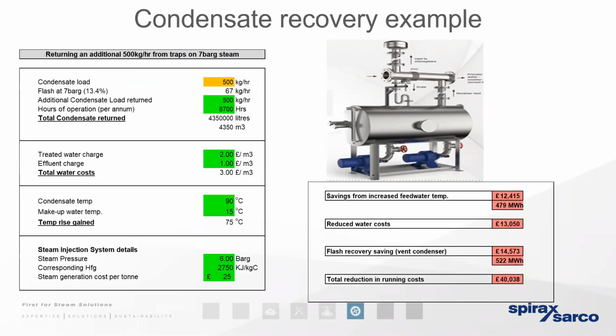So we've previously discussed condensate management in quite some detail. We know that condensate, in many cases, has got to be pumped back if it exists at a low pressure. So we've got to protect those electrical pumps. We've got to let the condensate fall to 0 bar gauge to avoid pump cavitation. So that flash steam's got to be vented away. And we also know that if we know what the pressure drop is, we can calculate how much condensate as a percentage is going to change state to flash steam.